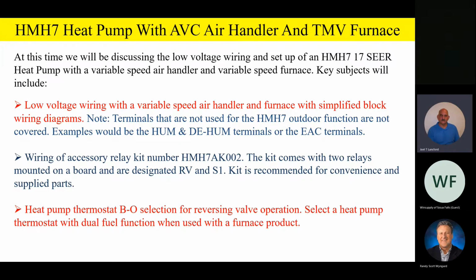So they had a situation where they didn't have the 002 kit. They wanted to know if they could make up their own, or could they use 2 001 kits? And the answer is yes, you could. The only thing is if you use 2 001 kits, you'd end up with 2 filter dryers, which I guess you could put on your truck, and some extra harnessing. But kind of keep that in mind that the 002 kit is nothing more than 2 relays available on that board. One of them is going to be RV. The other one's going to be the S1 relay for airflow reduction.